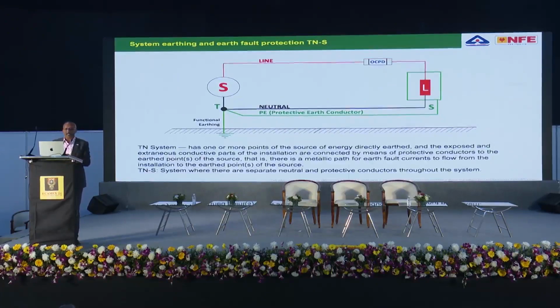It is a very simple definition, and you can see it here. This is from IS 3043. A TN system has one or more points of the source of energy directly earthed, and the exposed and extraneous conductive parts of the installation are connected by means of a protective conductor to the earthed point of the source. That is, there is a metallic path for earth fault current to flow from the installation to the earthed point of the source. There is a metal fault return path. Then only your MCB will trip. So that is what is shown here.